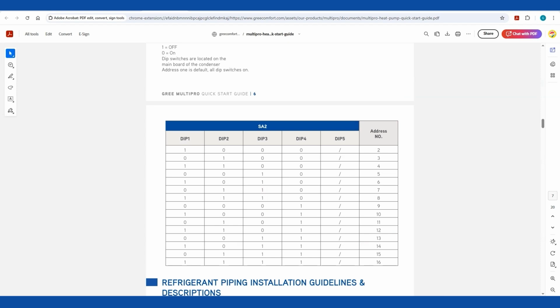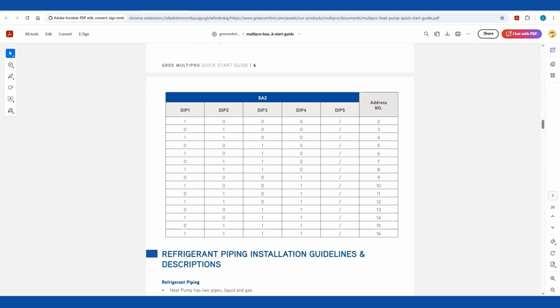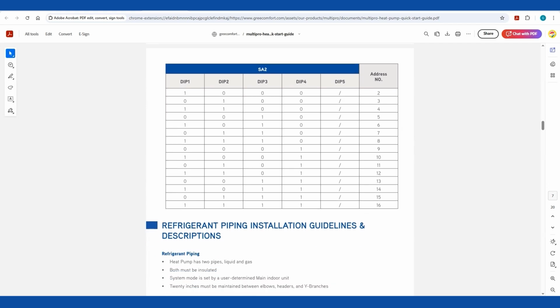GREE's a little different. 0 means on, 1 means off. So if I'm going to make my second unit be unit number 2, all I've got to do is turn dip switch 1 off. The rest remain on. That becomes unit number 2. If I've got 3 units, then I would set the third unit's dip switch 2 off and leave all the rest of the dip switches on, and so on, all the way up. We can combine up to 16 outdoor units. So just kind of an FYI of how you save yourself some headache later on.